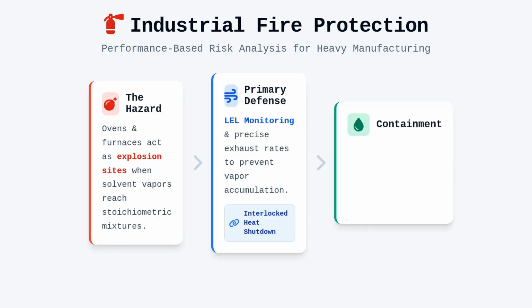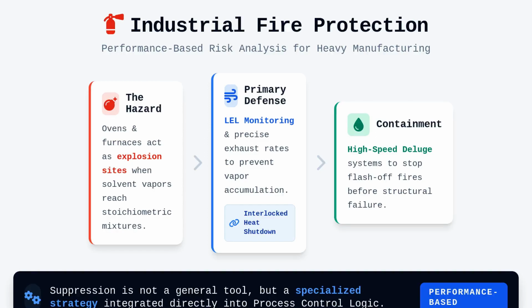When internal fires do occur due to flash-off from coatings, these enclosures often necessitate high-speed deluge systems to suppress the fire before structural integrity is compromised. You should view these systems not as general suppression, but as specialized containment strategies integrated directly into the process control logic of the manufacturing line.